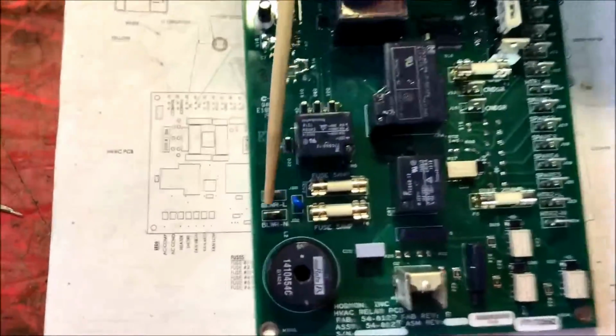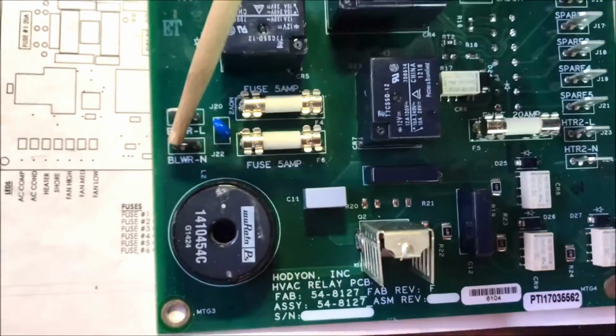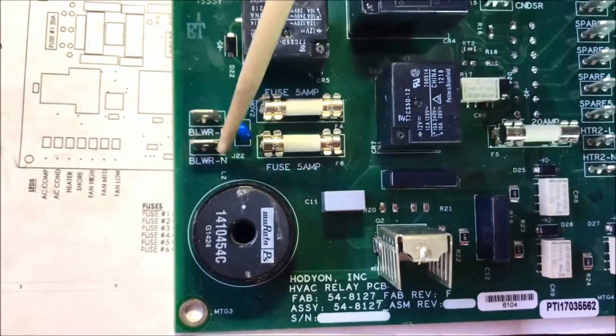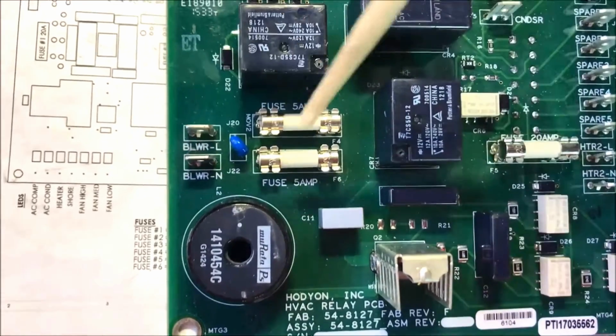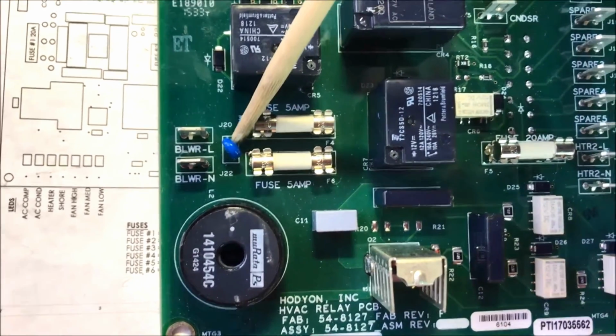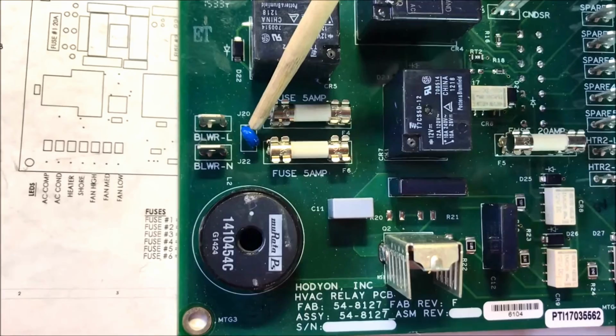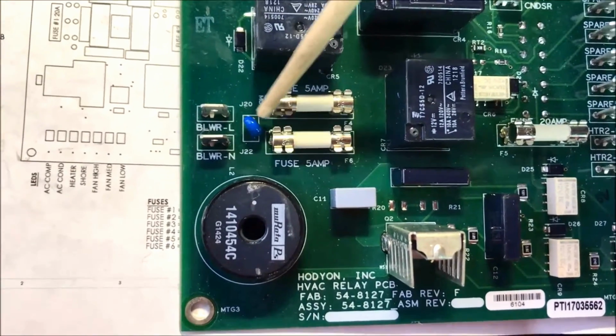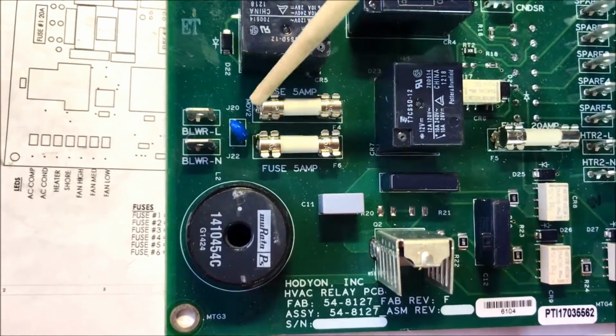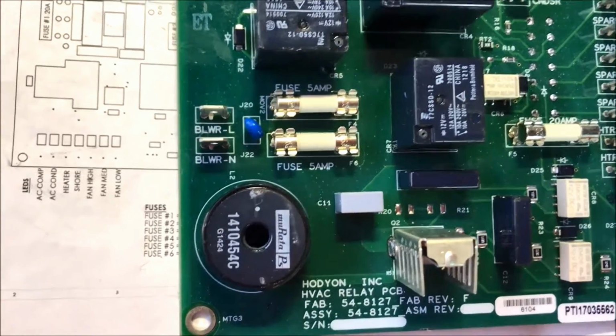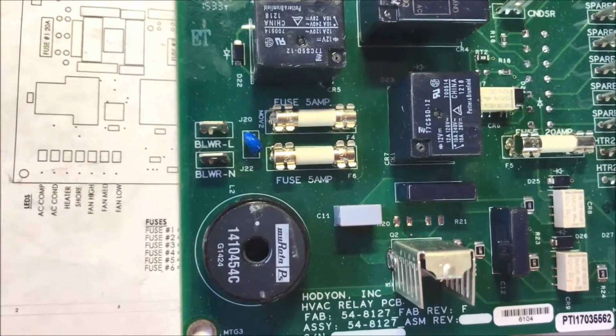The circuit board also has the power connections for the blower inside the HVAC, one in here. This is a normal condition of a metal oxide varistor. It should be shiny and all together, not split open or discolored and burnt.